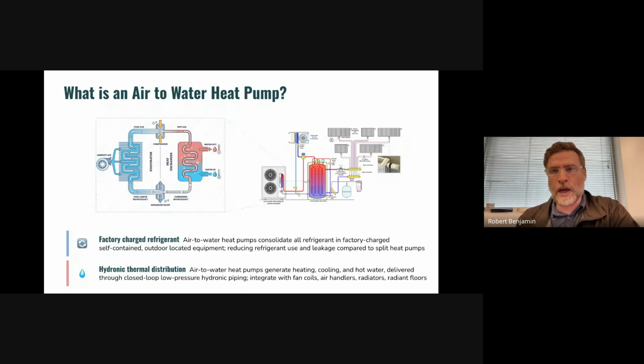But the big difference is that we go through, in monoblock configurations, a plate heat exchanger, using a hydronic loop to transfer energy inside the building envelope, which lets us do a lot of amazing things. We can do combi systems that do heating, cooling, and hot water from the same outdoor unit, and use all the different kinds of heat emitters available when you have water. So from a system point of view, there's lots of reasons to do it this way.